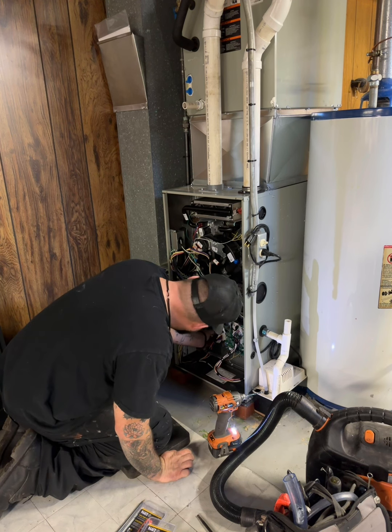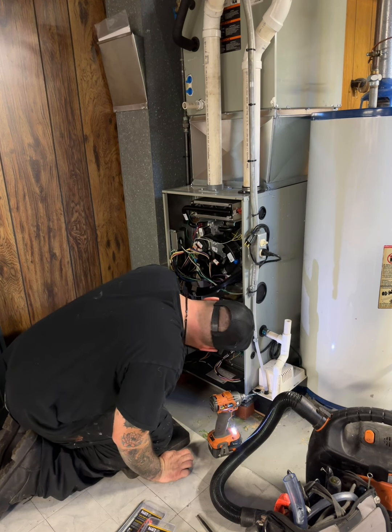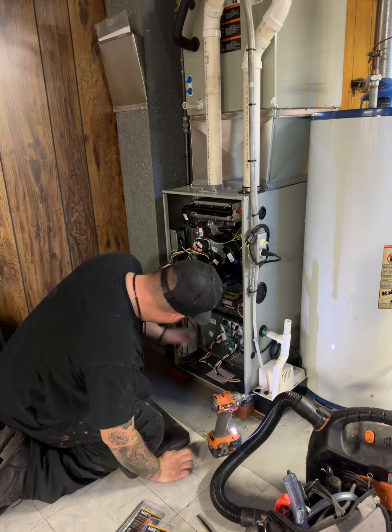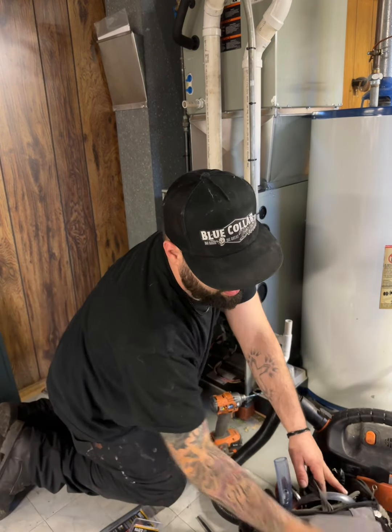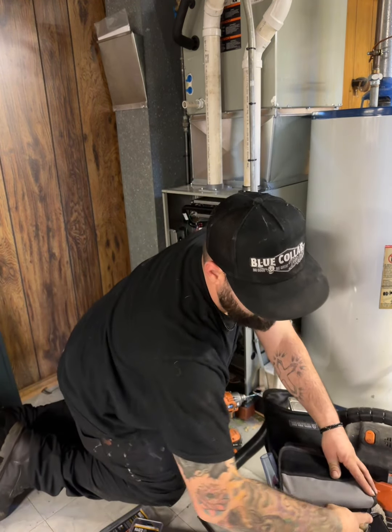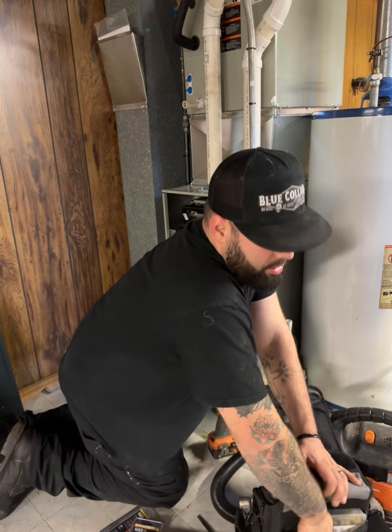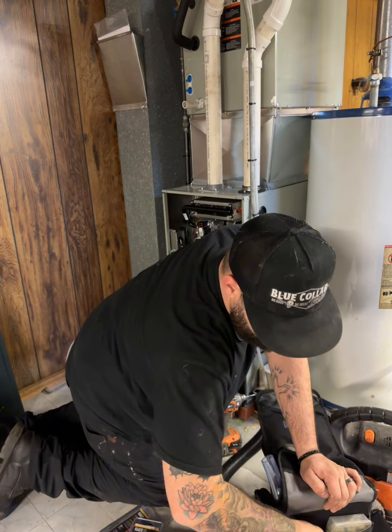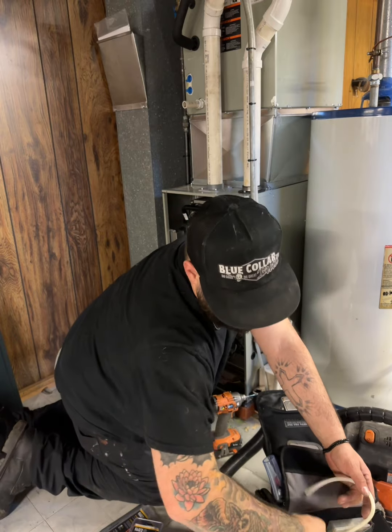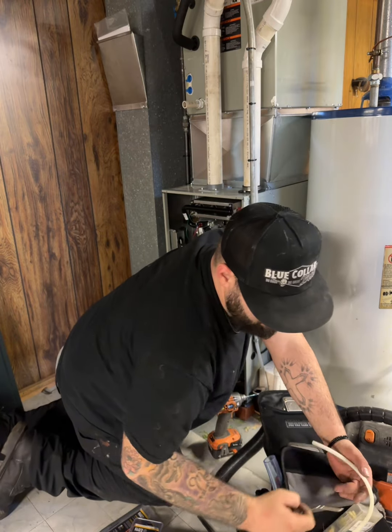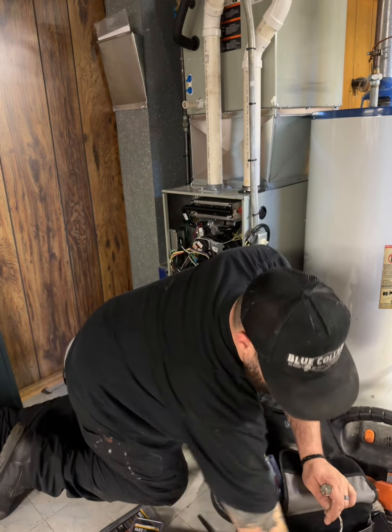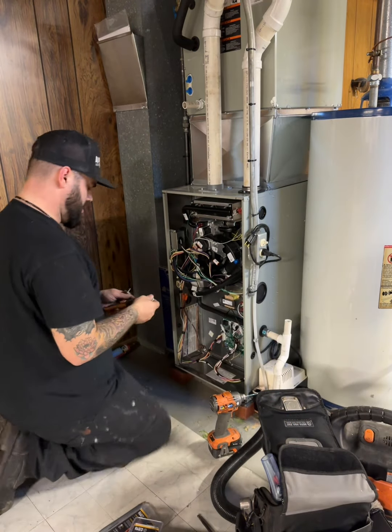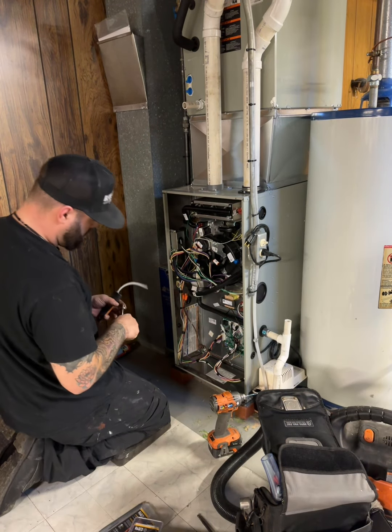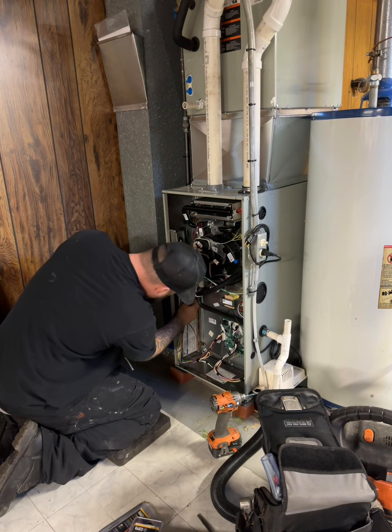Now I am going to go after the filter. I'm just checking the static on the furnace itself. I'm going to note that, so if I see any changes in service history, I can reference what this furnace was doing on startup day one—maybe they did a remodel, cut some returns, and made the static bounce up.